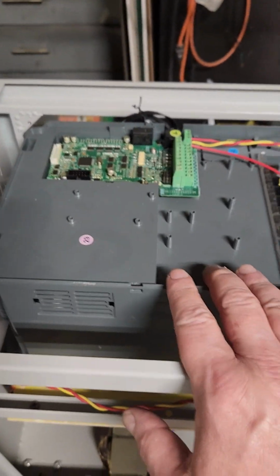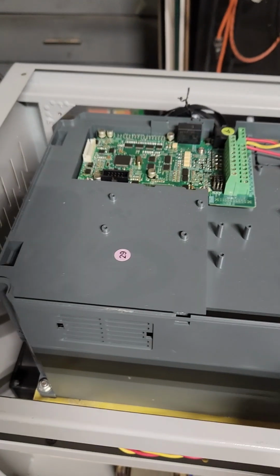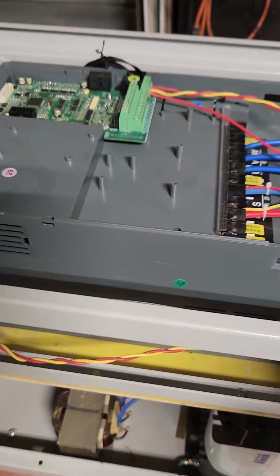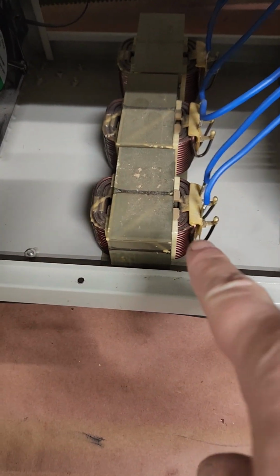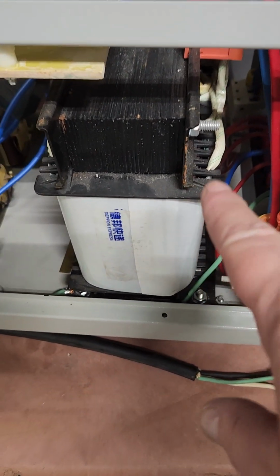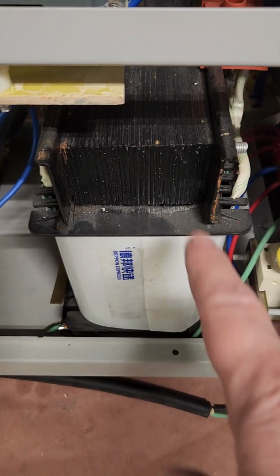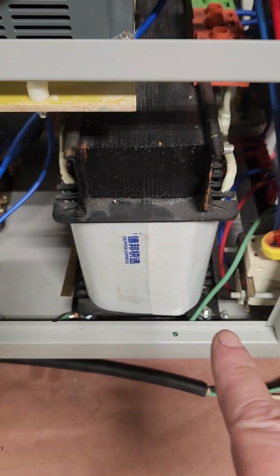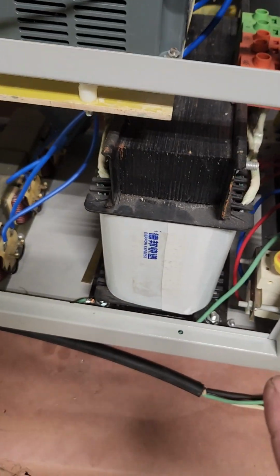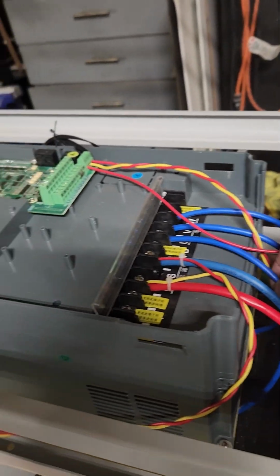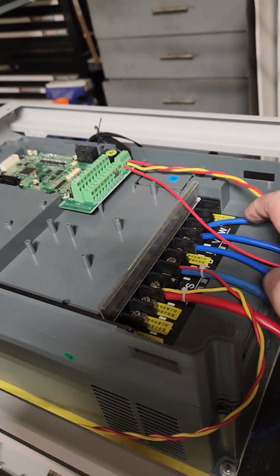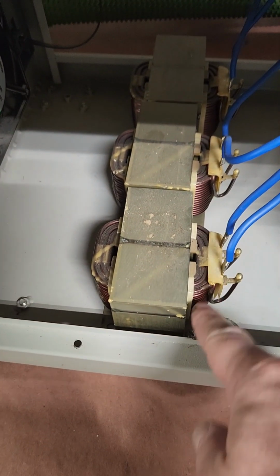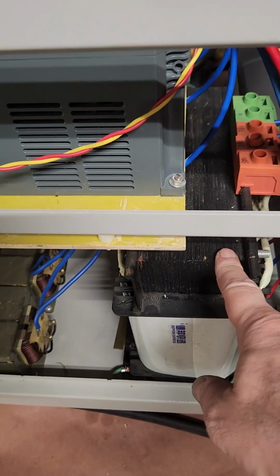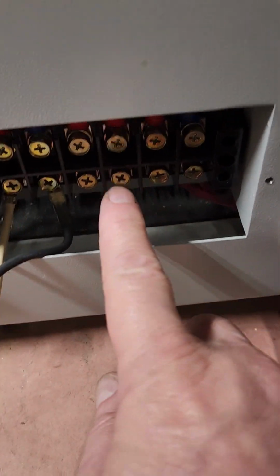The way they build this, they put a regular VFD, this is a 14 kilowatt VFD, can go to 500 hertz, so I can power a motor here, quite powerful. They run through some chokes and this transformer, but it's not wired as a transformer, not as an auto transformer and not as an isolation transformer. It's actually wired like some sort of filter. So the outputs, these three wires are the three phases UVW, each one goes into one of these chokes, then into the coil, and also comes out at the exit here through this switch.